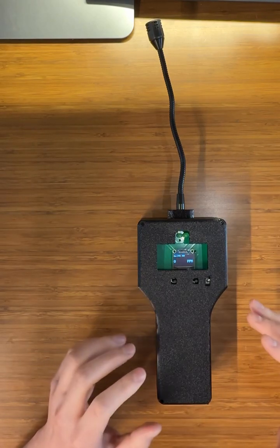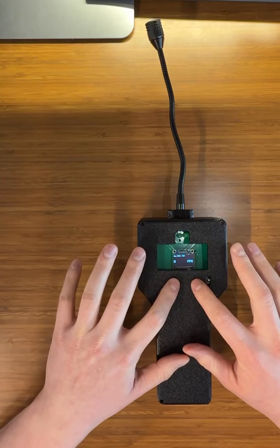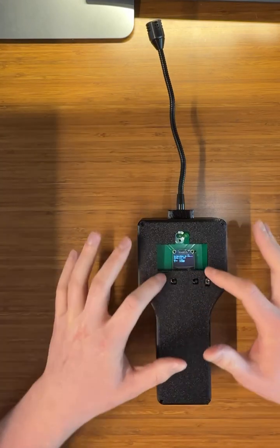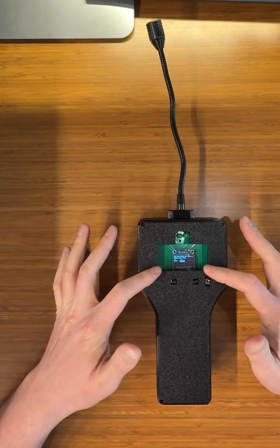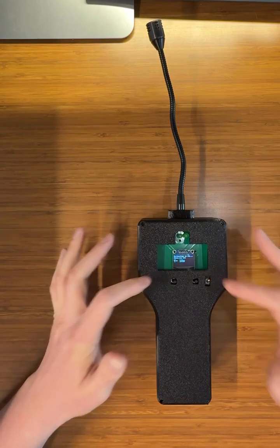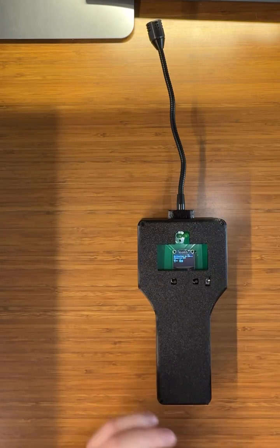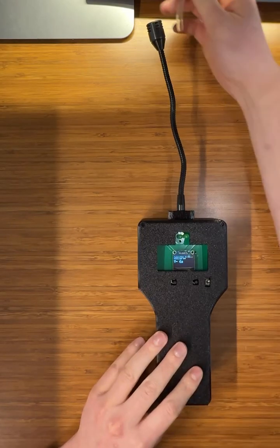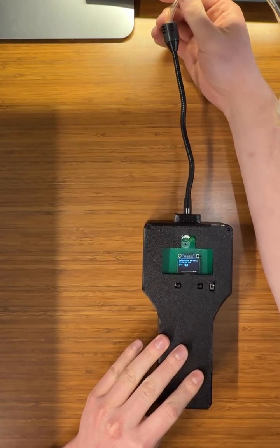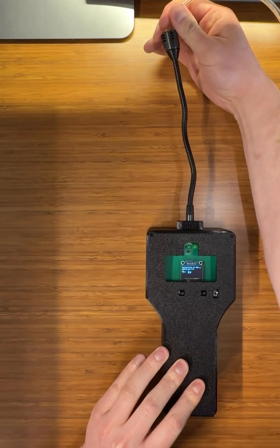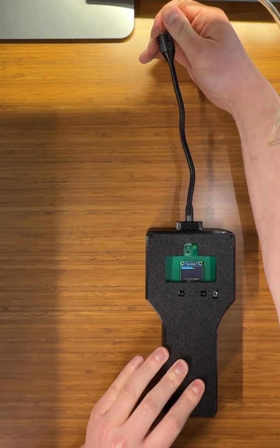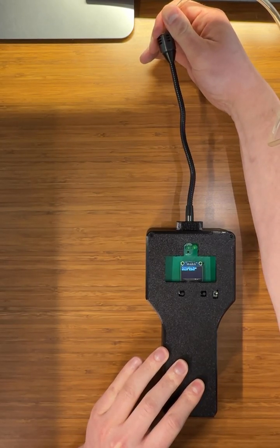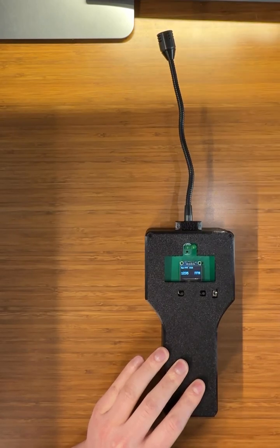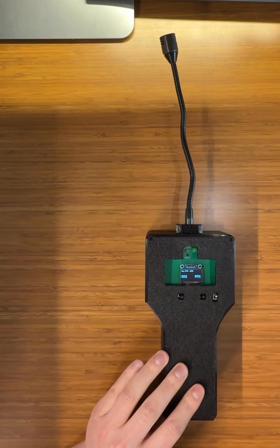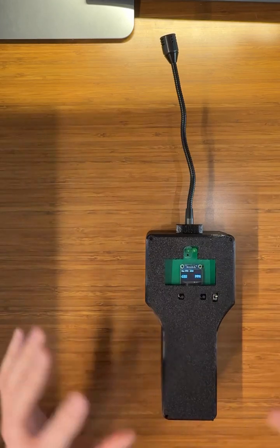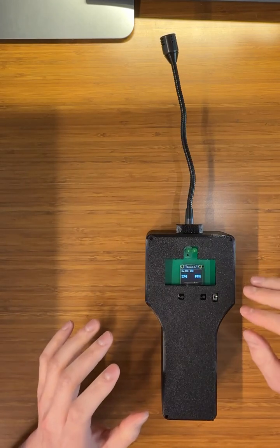Now moving on to the calibration side of things, the way that works is you press both of these buttons and you get a countdown. It says calibration in 15 seconds, apply gas now. So what you do is you apply the gas to the end of the housing. We don't have that housing, but you apply the gas to the end and hold it there until it says it's complete. So right now it's calibrating. It is taking the input voltage from the sensor and then sets an offset. It'll come back down as soon as the gas dissipates in the sensor area.